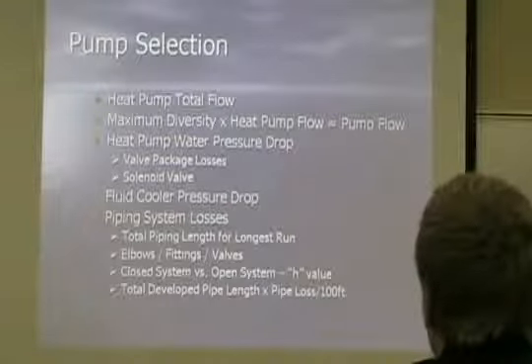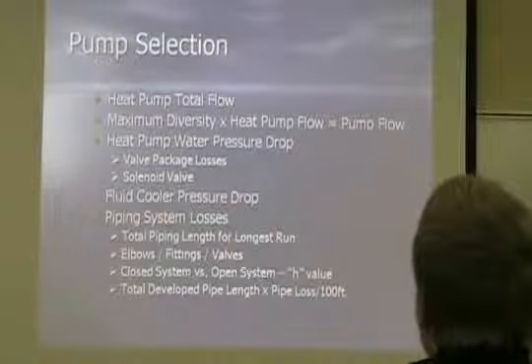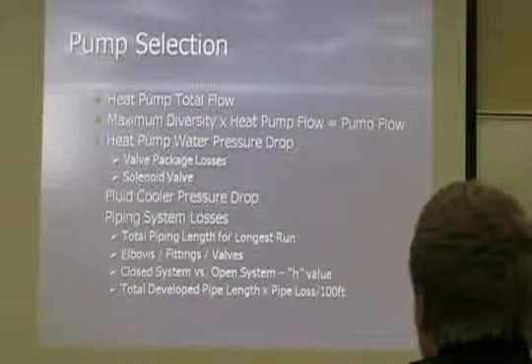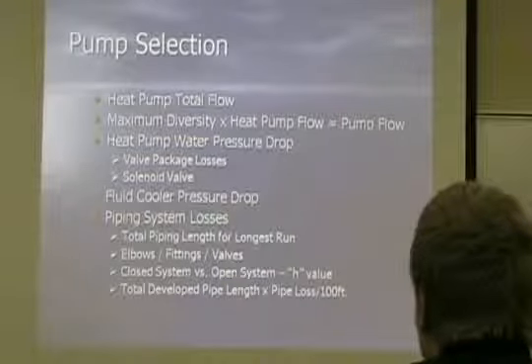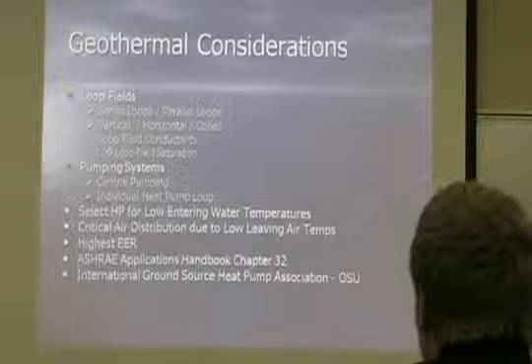Take the pressure drop of the system, plus any load that you've got on, say, your valves or solenoids, that's going to add pressure to your system. Fluid cooler pressure drop, and the piping system losses. Develop your total head and size your pump. We're going to talk about that next week. Geothermal applications.